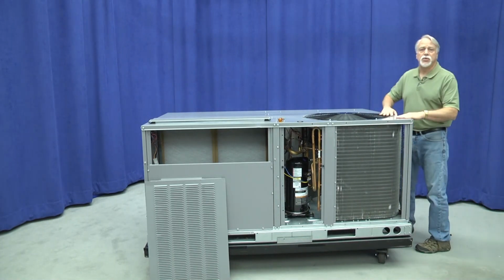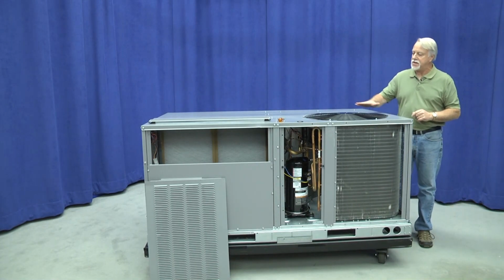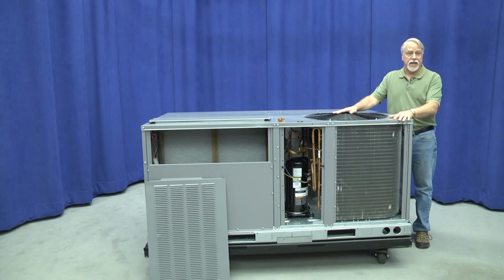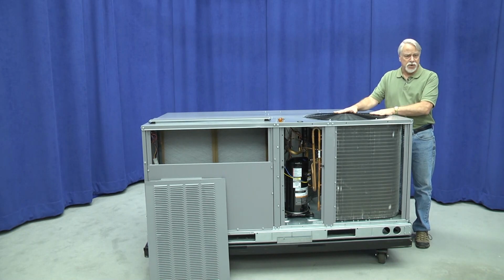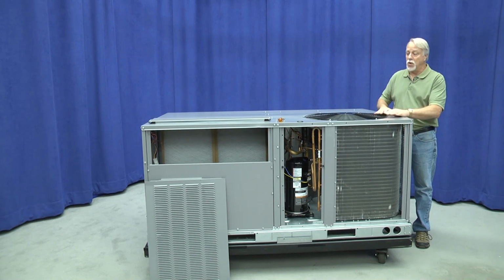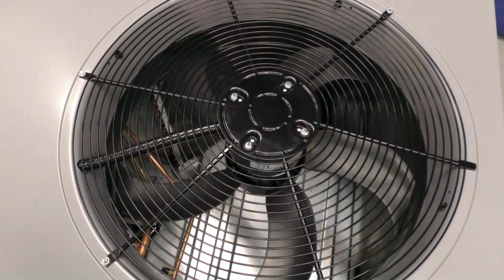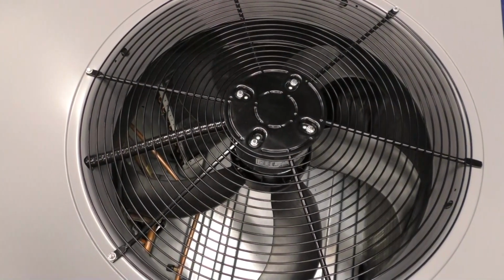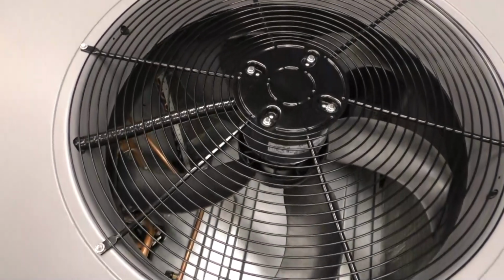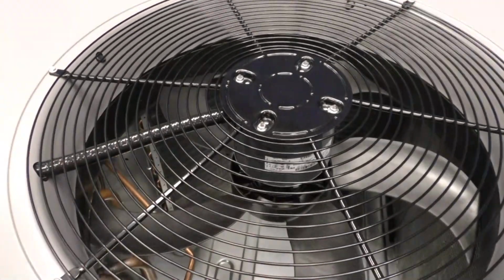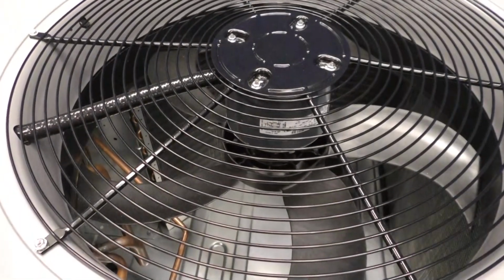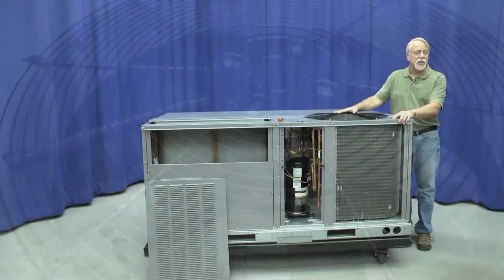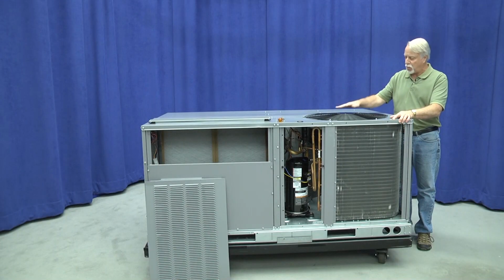One other little change with this particular machine anyways is the condenser fan. The motor itself is no different, however the condenser fan is moved to a composite prop. The orifice is slightly different. They're designed to work together, and the alignment instructions for replacing that particular prop, should the motor have to be replaced, are in the installation instruction service portion of it.